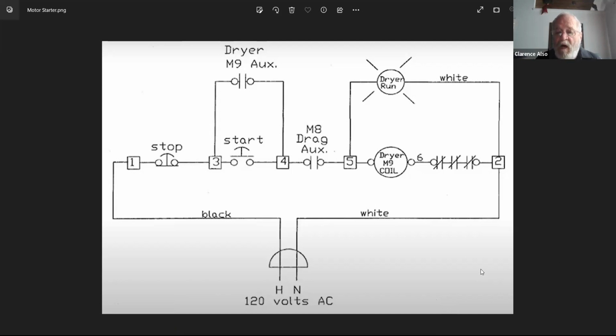Isaac was saying, well, we got to test the meter to see if it works. If we're going to test the meter, we're going to go to a known place where we're expecting voltage at. That terminal number 1 goes right there to that hot side of the plug, so that's a very easy place to be checking it. So if you're going to test your meter, Isaac was saying he wants to test it out. Is that a good place to be testing out, terminal number 1, Isaac?